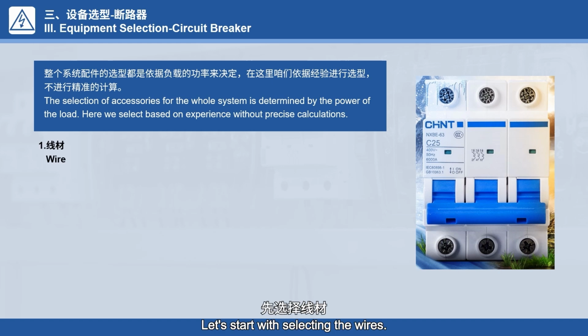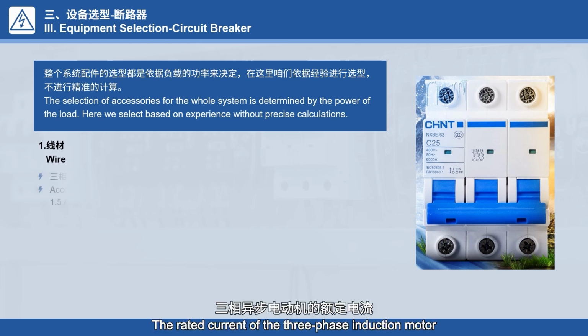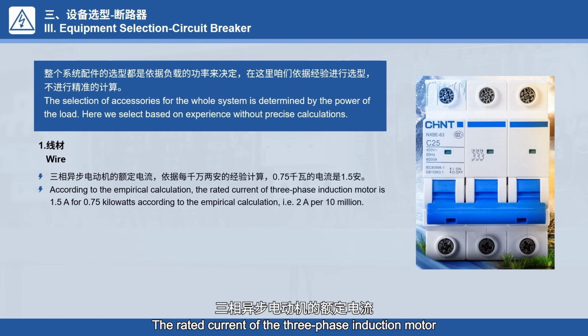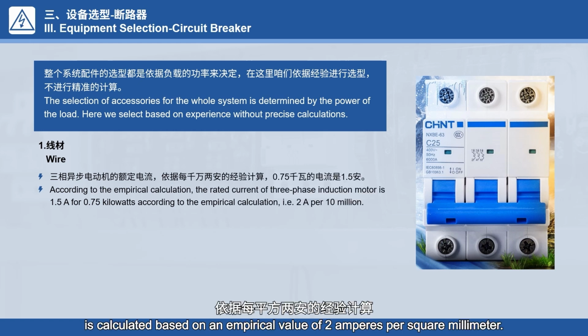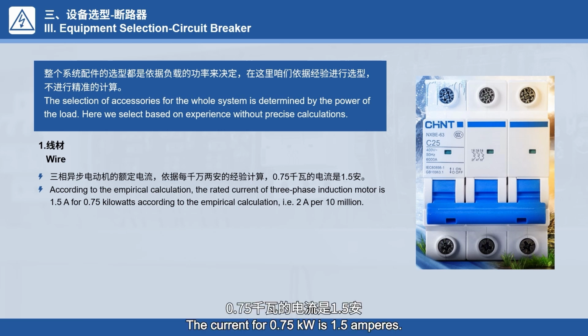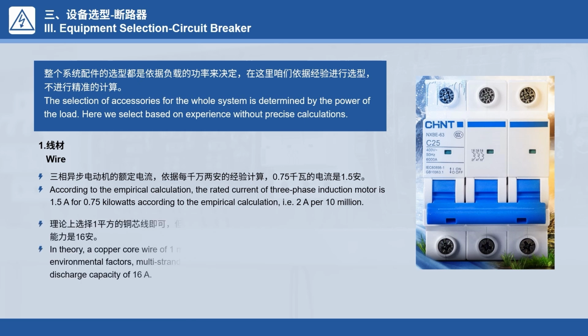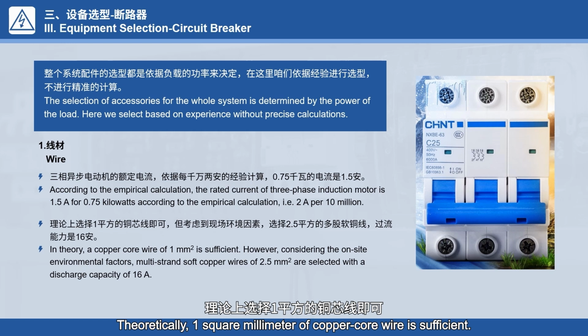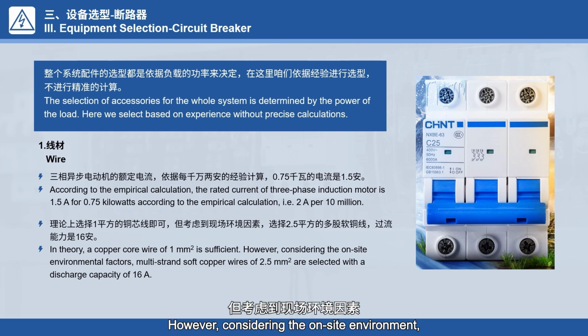Let's start with selecting the wires. The rated current of the 3-phase induction motor is calculated based on an empirical value of 2 amperes per square millimeter. The current for 0.75 kilowatts is 1.5 amperes. Theoretically, 1 square millimeter of copper core wire is sufficient. However, considering the on-site environment, we choose 2.5 square millimeter multi-strand soft copper wire with a current carrying capacity of 16 amperes.